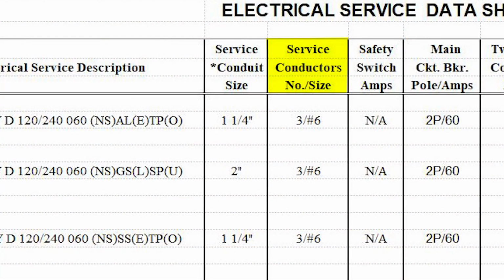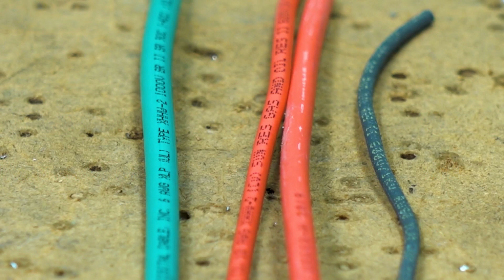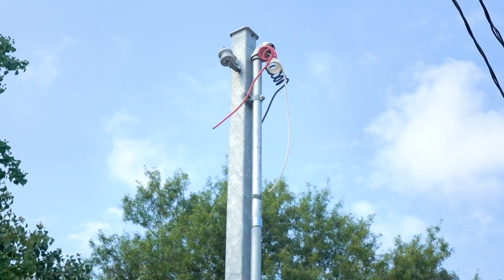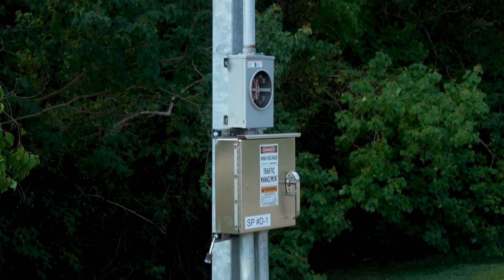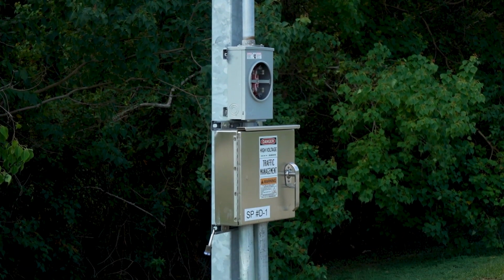Those are found in the 5th column of the chart under the title Service Conductors, Number and Size. To verify that the proper size of conductors was installed according to plans, the inspector will find the size of the insulated electrical conductor by locating the AWG size printed in small letters on the conductor's insulated jacket. Next, we will inspect the utility company's electric meter socket enclosure. The meter socket, or meter base, is installed during construction of the electrical service.